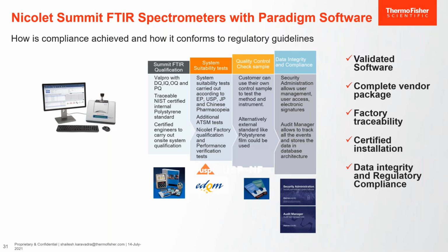We use a traceable NIST certified internal polystyrene standard to qualify the system, and certified engineers carry out the on-site system qualification. All the system suitability tests are according to various pharmacopoeias, and we can run some additional ASTM tests as well. We provide full factory qualification and performance verification tests.